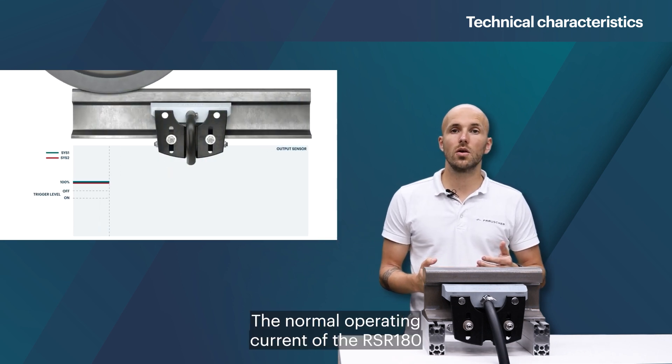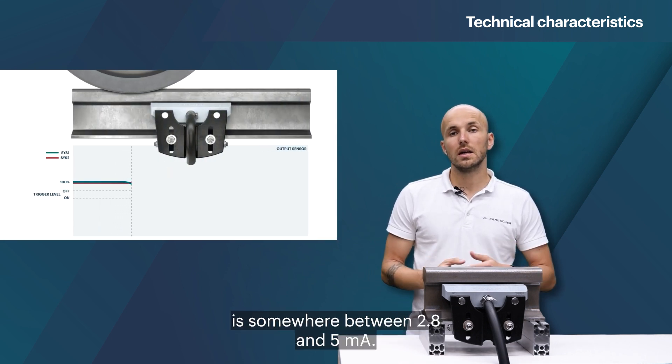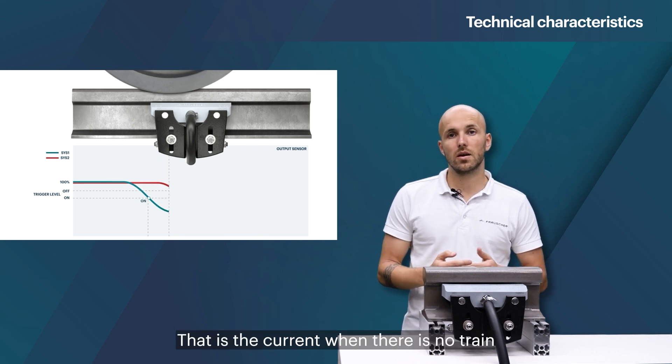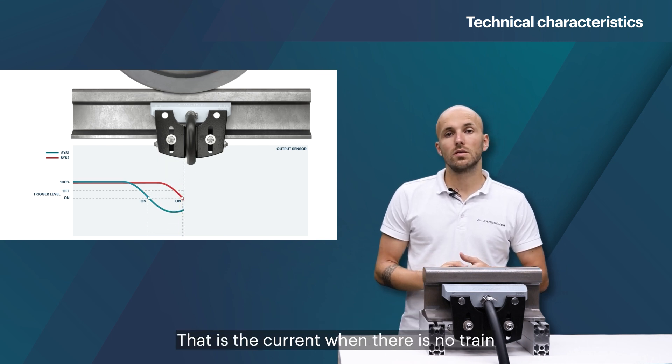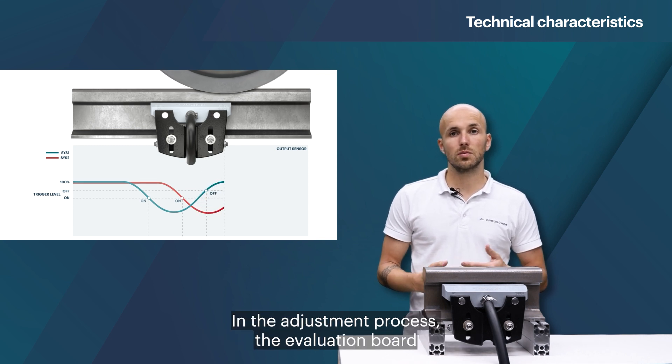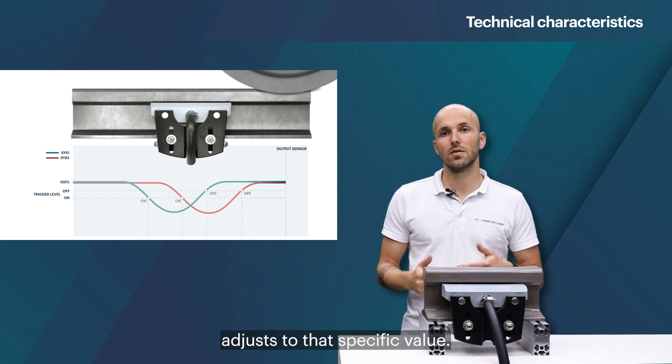The normal operating current of the RSR 180 is somewhere between 2.8 and 5 milliamps. That current is when there is no train or metal object in the proximity of the wheel sensor. In the adjustment process, the evaluation board adjusts to that specific value.